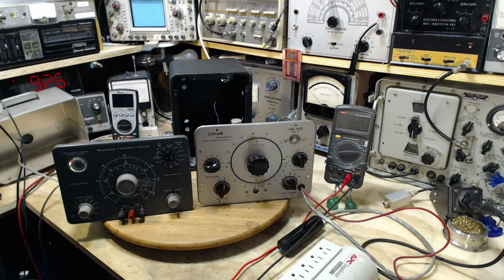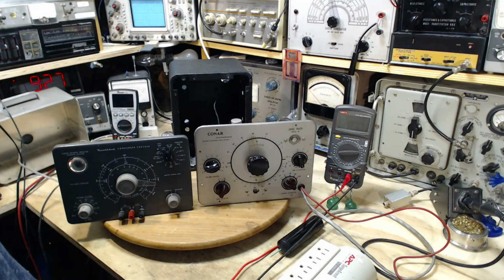So in my experience on the power system, the only serious surge worth considering was a case - an unusual case - where a high voltage supply line contacts a lower voltage supply line. The power protection fails to operate, so the circuits continue operating, and the high voltage is impressed on the low voltage, and then it goes, well, who knows where from there, right?